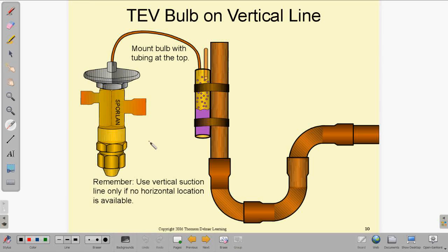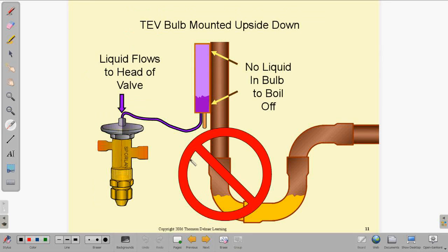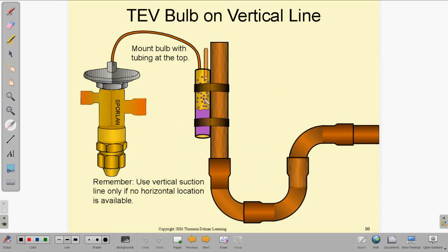Now the TXV bulb on a vertical line, you don't want to do that if you can help it. It's designed to be on the horizontal, but it will work on the vertical. But you must pay attention, because if you mount it the wrong way, you have liquid going back down to the top of the diaphragm, and it's going to throw the sensing bulb off, because there's no liquid in the bulb to boil, because most of it will have drained down into the top of the TXV, and that's going to throw things off too. So always make sure that you mount it with the outlet of the sensing bulb and the tubing at the top of the bulb.